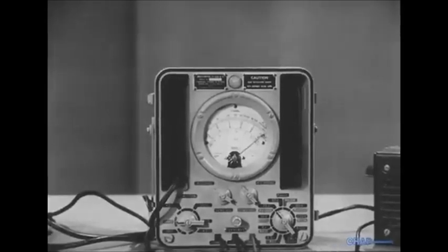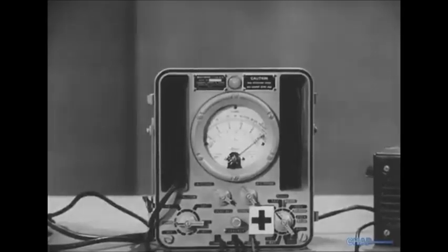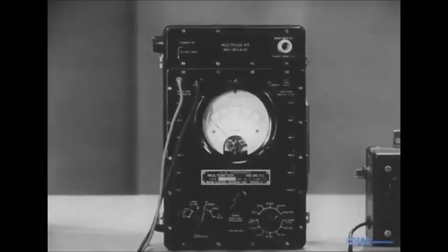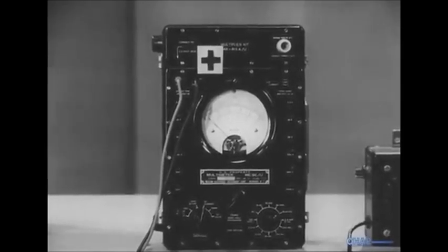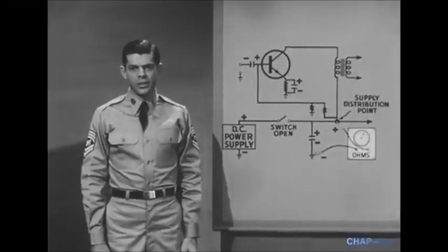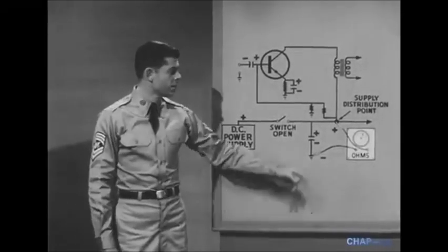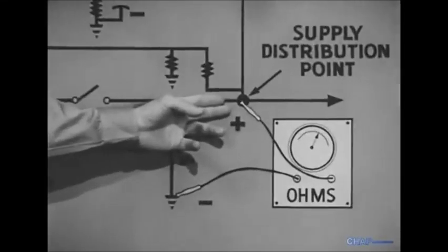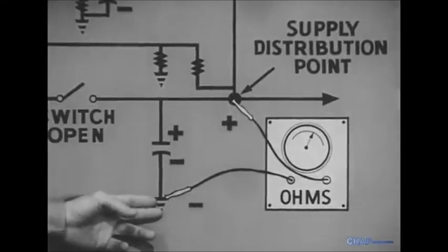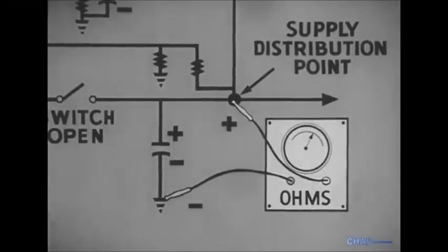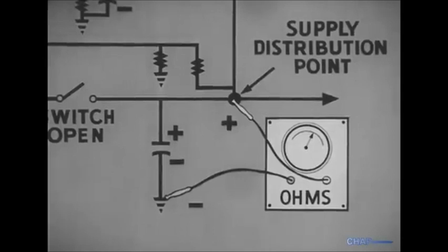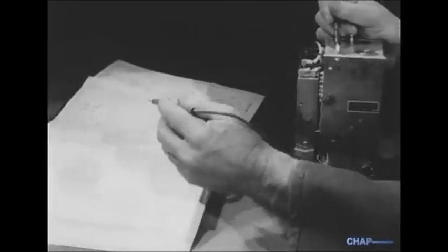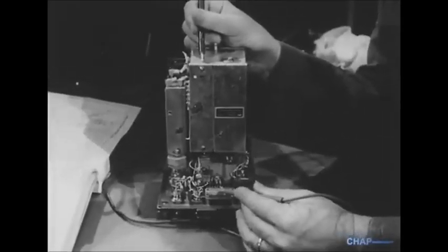On the electronic multimeter we're using, the TS505, the ohms probe is the positive probe. But on the familiar TS352 multimeter, it's the common probe that's positive. In the example here, whichever probe is positive is applied to the supply distribution point. The negative probe goes to ground. Under operating conditions, the supply distribution point in this diagram would always be positive with respect to ground. In this case, resistance readings at checkpoints are satisfactory.